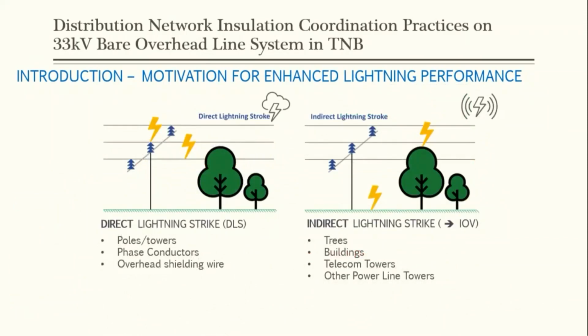There will be two kinds of overvoltage due to lightning. One is direct lightning strike, and another one is indirect lightning strike, or the induced overvoltage, right? Direct lightning strike can happen to our poles or towers, and phase conductors will be the most dangerous, and of course the overhead shielding wire. Induced overvoltage can be due to lightning hitting the trees, buildings nearby, telecom towers, or other power line towers near the vicinity of our distribution overhead lines.